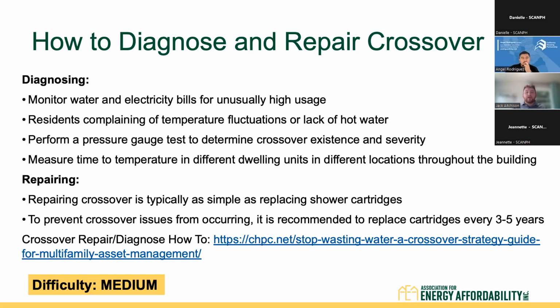Another sign is residents complaining of temperature fluctuations or lack of hot water. Perform a pressure gauge test to determine crossover existence and severity. A pressure gauge crossover test does require the cold water makeup to the boiler room to be shut off, and also draining of the hot water system, so you may want to have a plumber there with you. Measure time to temperature in different dwelling units in different locations throughout the building.